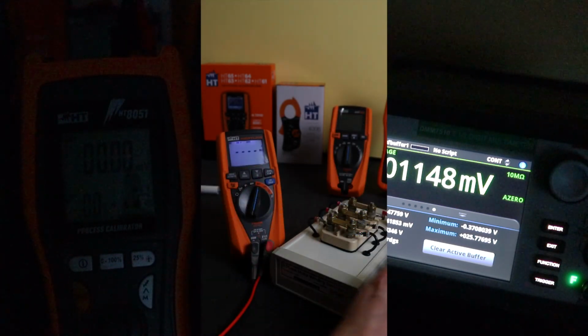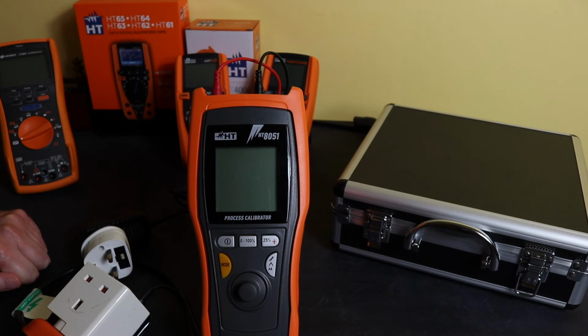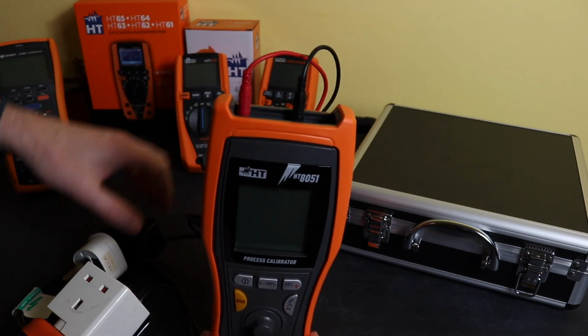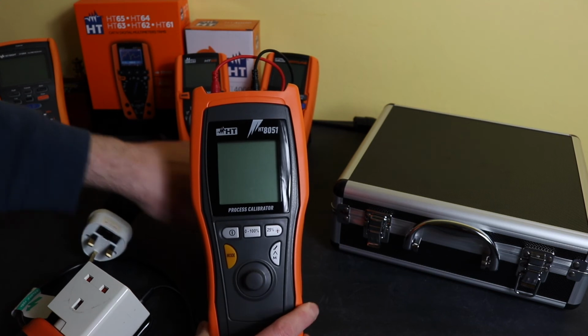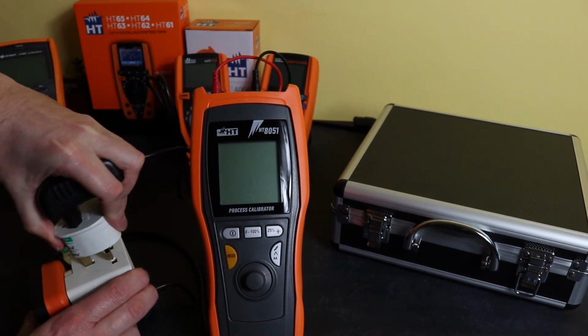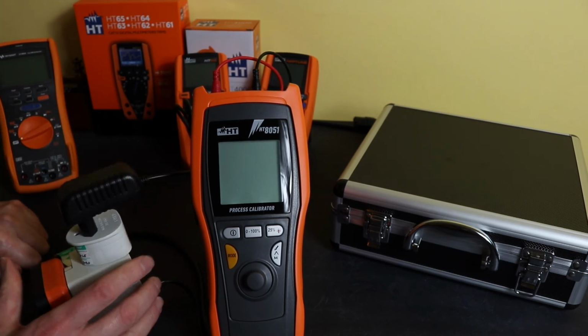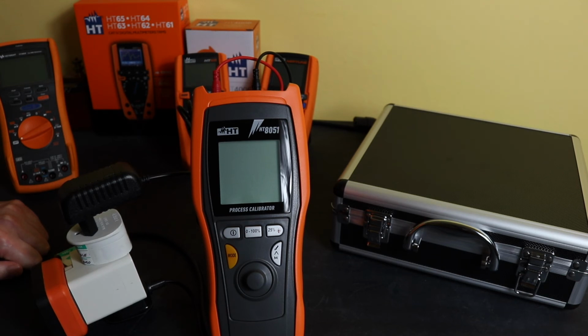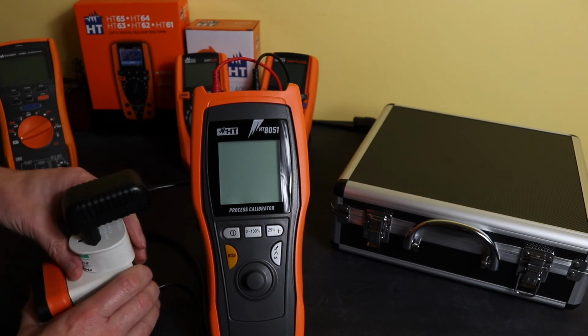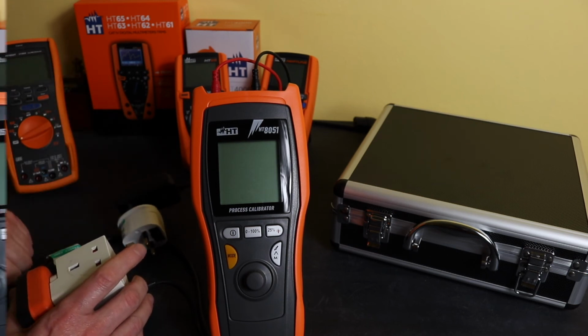You've just seen it gone out there. If you look at their other instruments, they do have really good backlights on them. It just doesn't seem to have been carried over to the HT8051 there. So the backlight is also the indicator that the unit is on charge. This has an internal PP3 9-volt battery on it. You can connect this charger that comes with the instrument in at two terminals at the top, and when you plug it in, you can see the screen has lit up, and that's the indicator to say that it's on charge. But you can see it's actually lit up and it's got more intensity than when you're using it as a backlight to display the readings. So yeah, it's a bit of a strange one, this backlight. I'll plug it in and hopefully you can see it flashes and then goes off again.